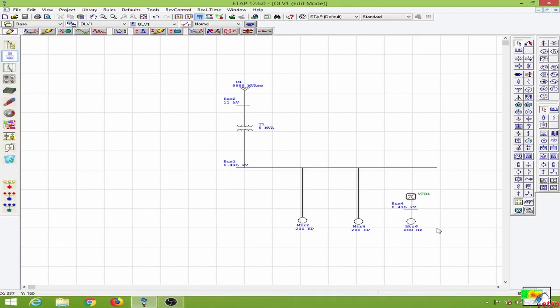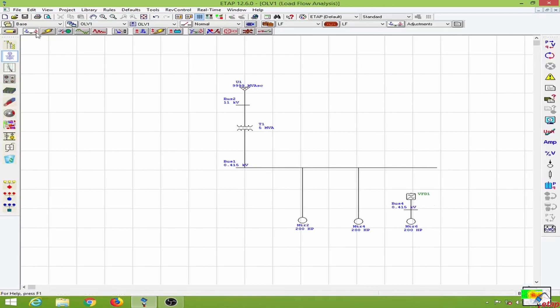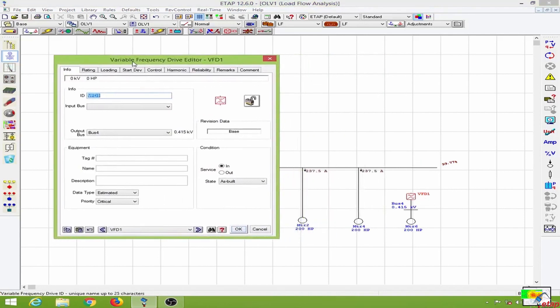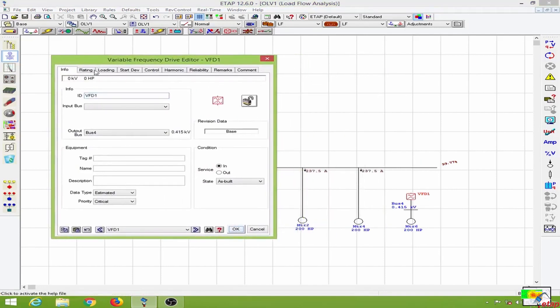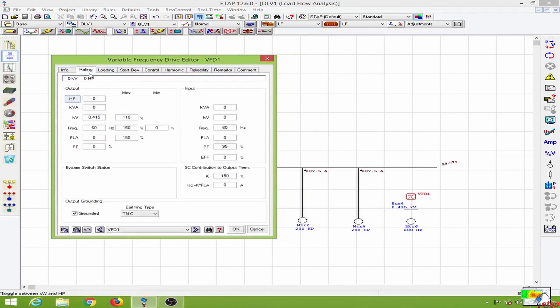In order to provide the ratings for the variable frequency drive, I will have to obtain the data from the load flow, so let us conduct a load flow. Now let us edit the variable frequency drive. This variable frequency drive editor pops up and we will go to the ratings page. We know the HP rating of the motor is 200 HP, and the full load current is 237.5 amps, which we have from the load flow analysis.